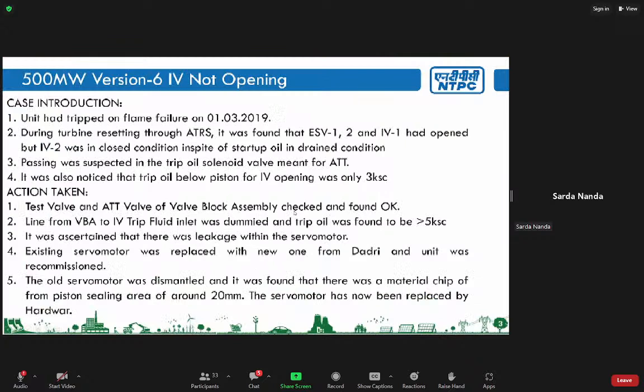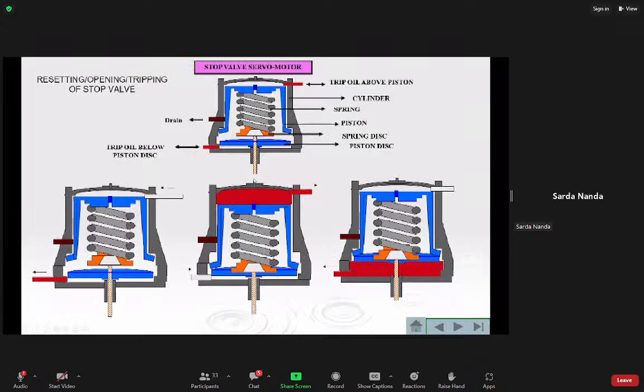Between the test valve and the stop valve, we found that once we dummied it before the stop valve, the test trip oil pressure was sufficient. That means there was some leakage within the servo motor. And in the presentation before mine, this particular slide was shown. I'll just tell you that the stop valve servo motor is the same for all kinds of 200 megawatt or 500 megawatt.